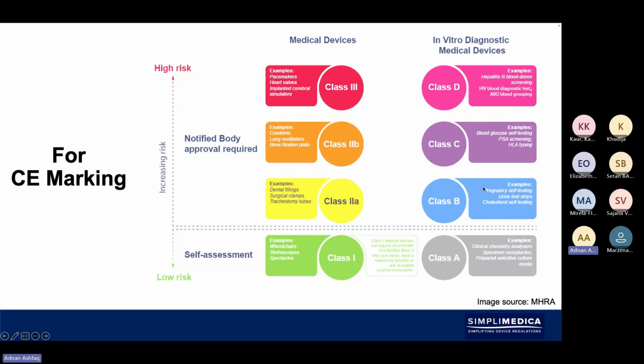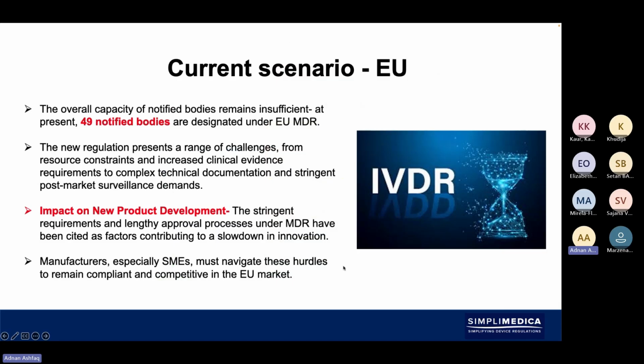And then we also have to follow the rules. Each of these has different rules. The current situation with the EU, I think that's a slightly older figure, but we have a few more notified bodies than that. But it's a big challenge at the moment with availability and capacity from notified bodies, because they're very busy transitioning anyone that's already been legally certified with an old CE certificate under the MDD to the new MDR. To give you a statistic, from last year, only about 10% of the certificates issued under the old MDD had been transferred to the new MDR.